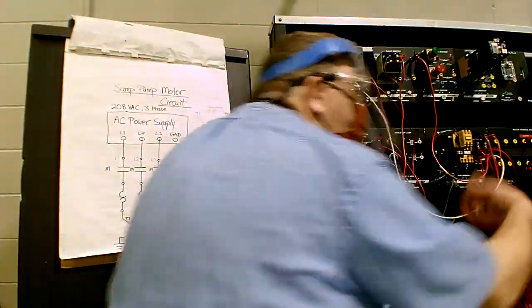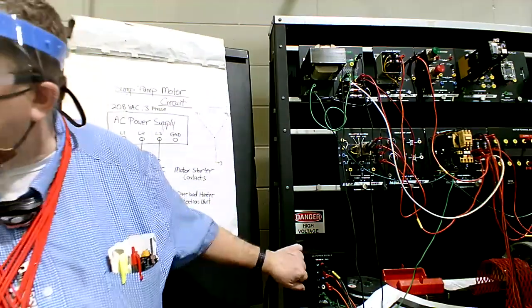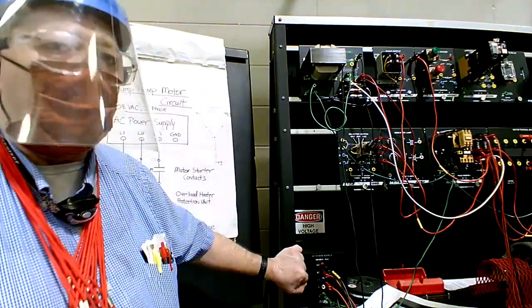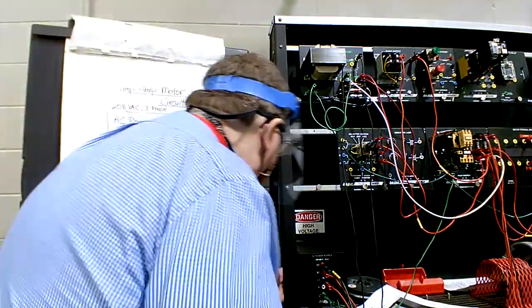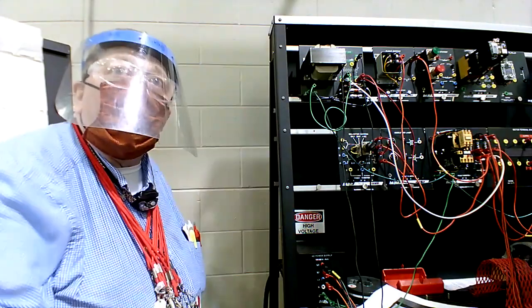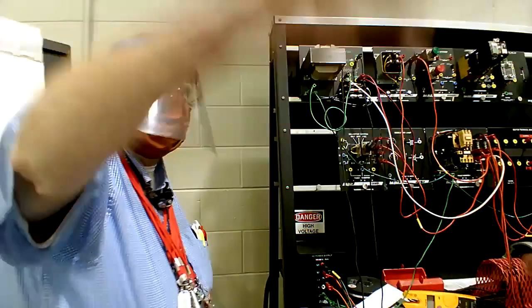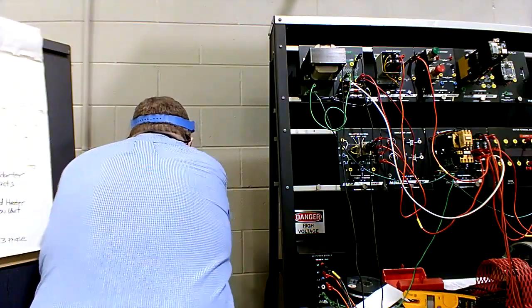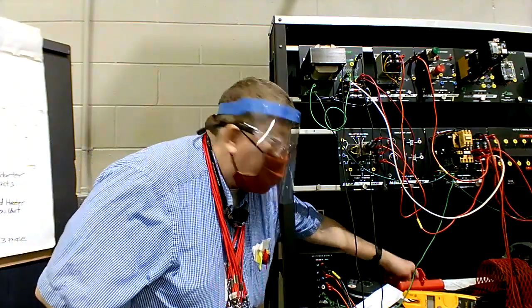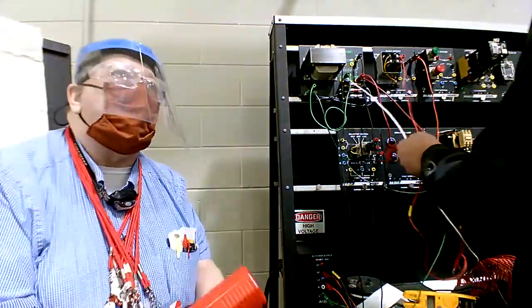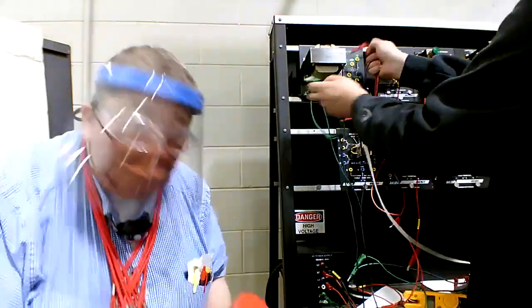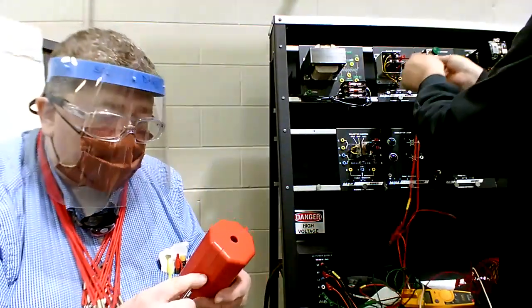Good. Okay, that's fine. You would normally have a nameplate, and you would refer to that. That nameplate's missing, but you've been seeing them all. You would go by that as far as your amps, what it should be doing. Now, this is freed up for someone that needs something to do. If you're way down on the list as far as being checked, we're checking you now. So get your PPE and we're heading your way. Yep. Right, Luke, if you unhook yours, but if somebody's back on the list, go ahead and grab this and do it. We're gonna be checking your plywood boards over there now.